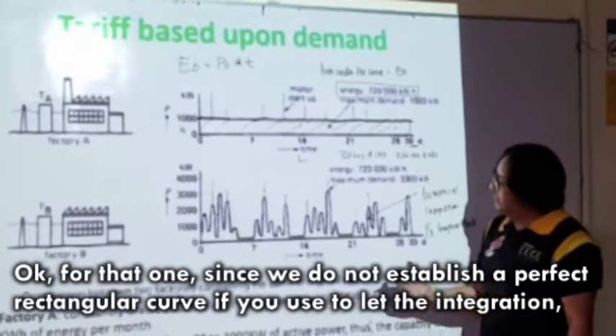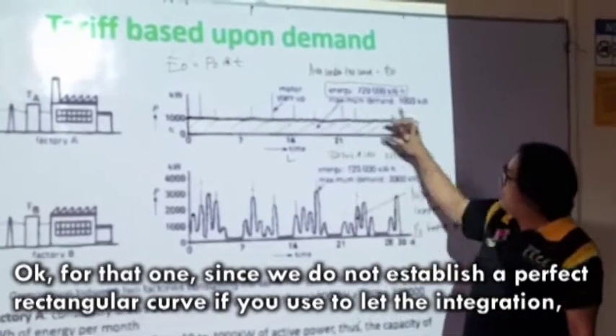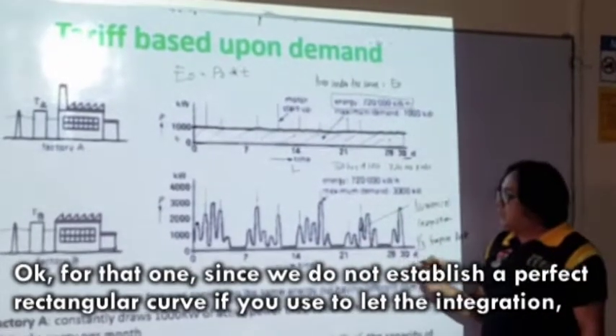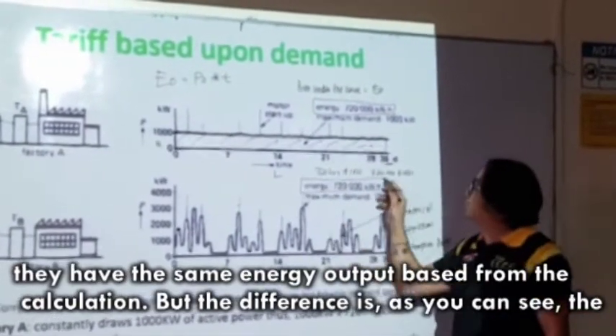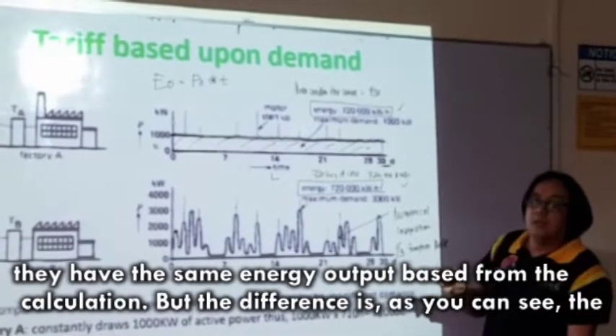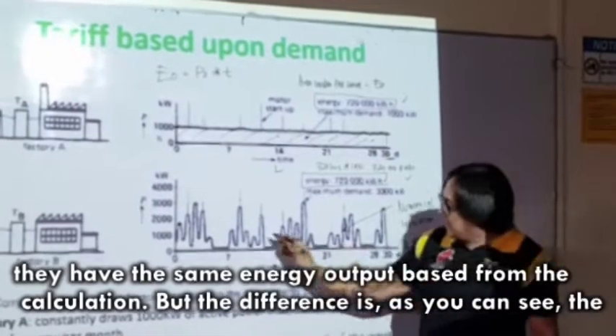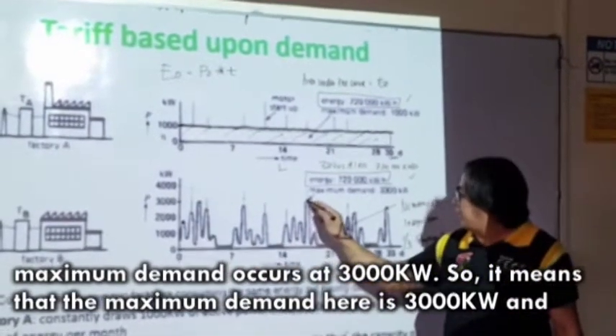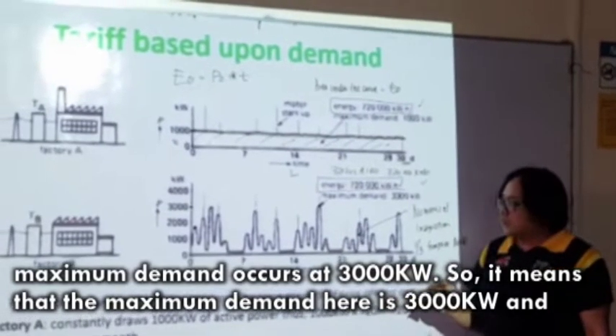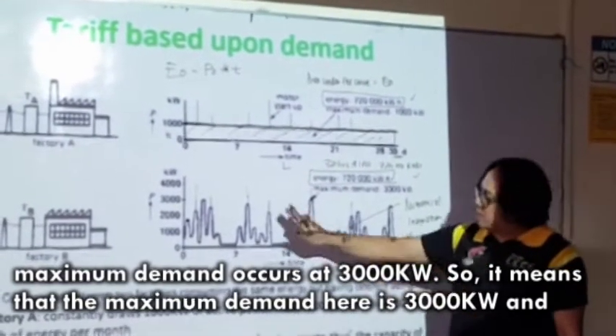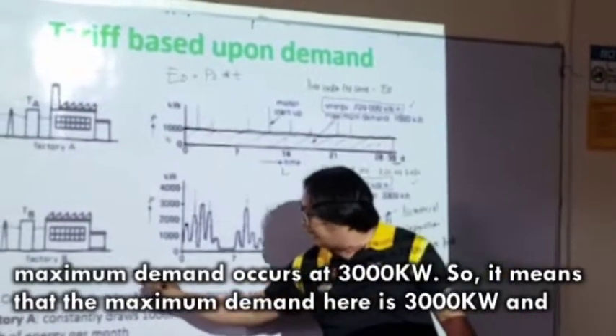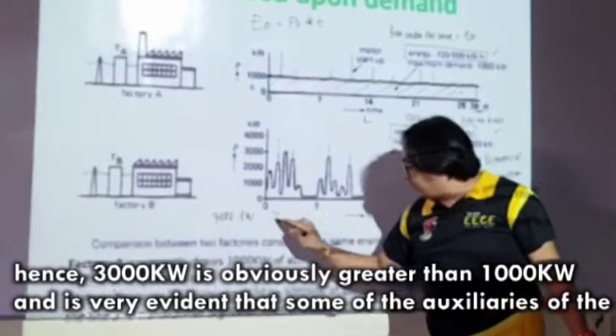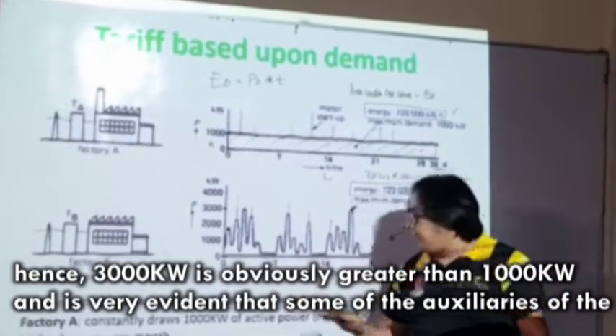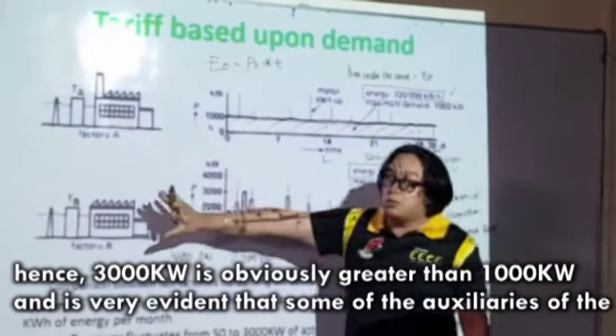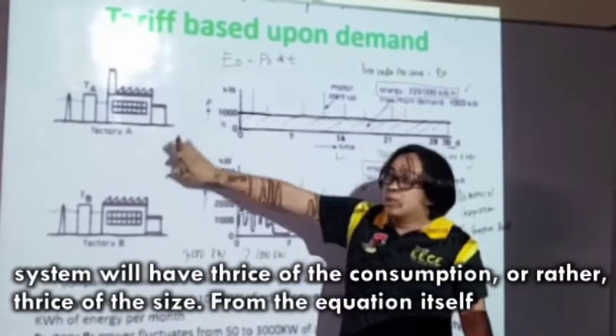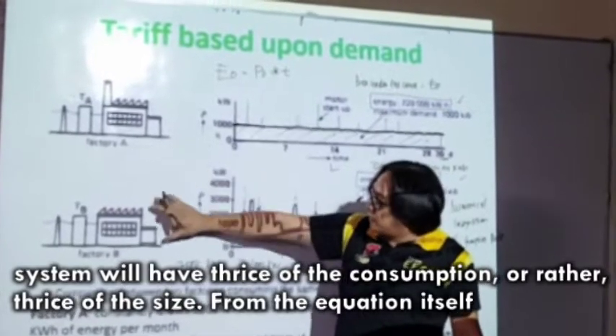Since we do not have a perfect rectangular curve, if you use numerical integration, they have the same energy output based on the calculation. But the difference is, as you can see, the maximum demand occurs at 3,000 kilowatts. So the maximum demand here is 3,000 kilowatts, obviously greater than 1,000 kilowatts, and it is very evident that some of the auxiliaries of the system will have thrice the size.